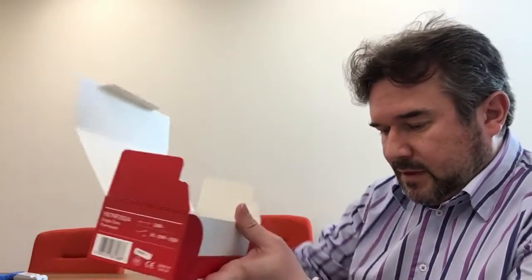Let's start with the Honeywell single zone thermostat. This recent addition comes in a box with a BDR-91 wireless receiver. Now these talk to each other using the Honeywell two-way wireless language. The control intelligence is actually in the thermostat and the wireless receiver is controlled by the thermostat to switch the boiler on and off according to the TPI cycle rate and run time. The thermostat calculates the heat demand and switches the relay on and off to produce the required output from the boiler. Remember, this is on the fixed flow rate temperature that's set up on the boiler.